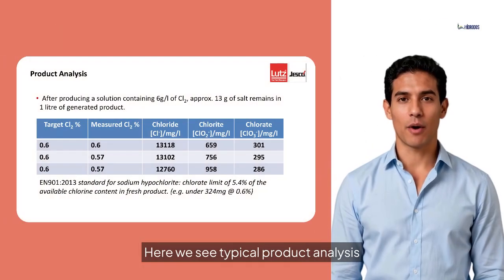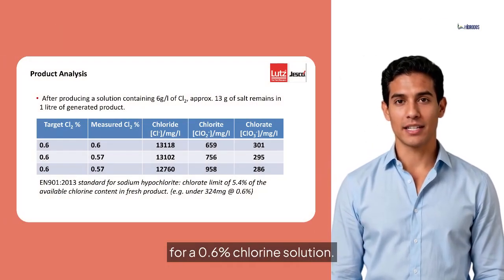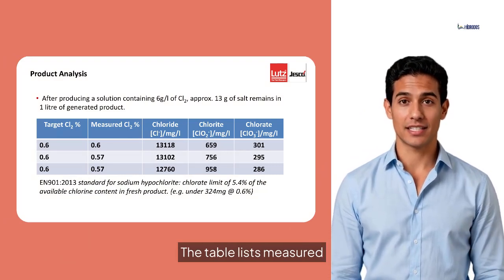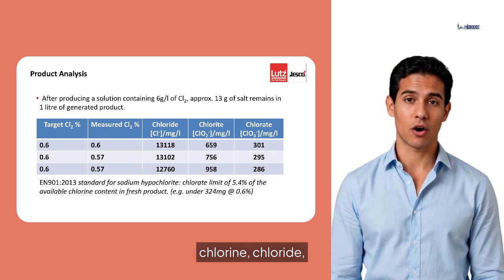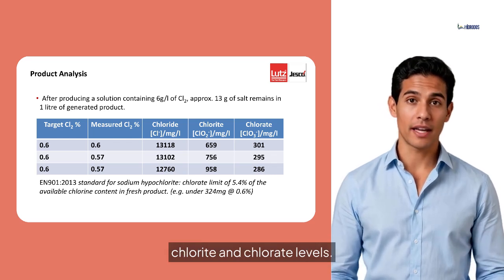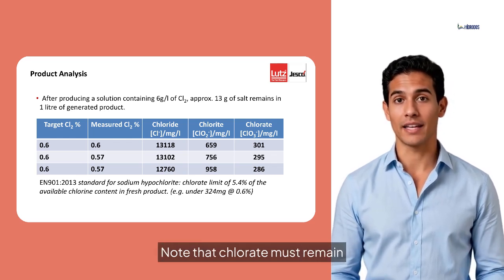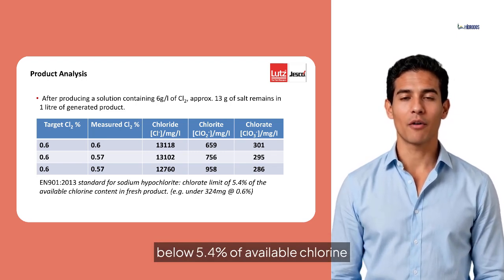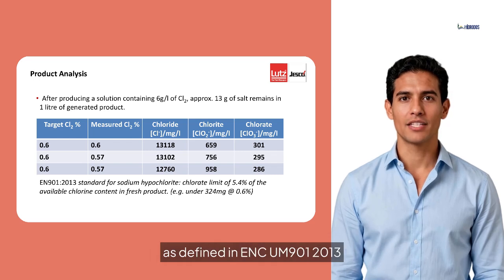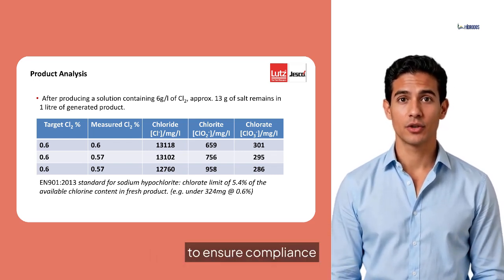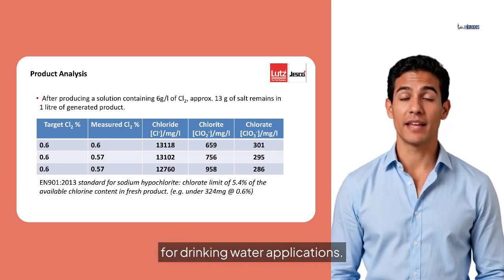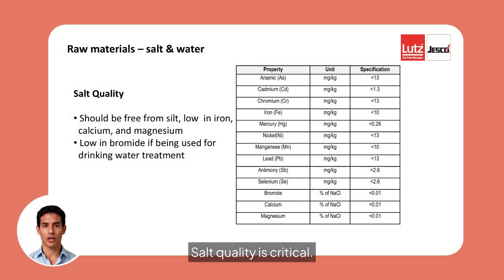Here we see typical product analysis for a 0.6% chlorine solution. The table lists measured chlorine, chloride, chlorite, and chlorate levels. Note that chlorate must remain below 5.4% of available chlorine, as defined in EN 901, 2013, to ensure compliance for drinking water applications. Salt quality is critical.